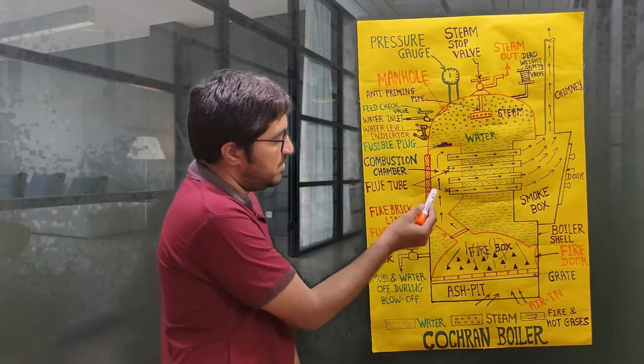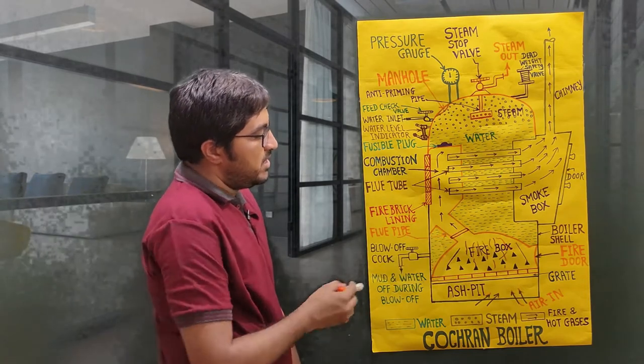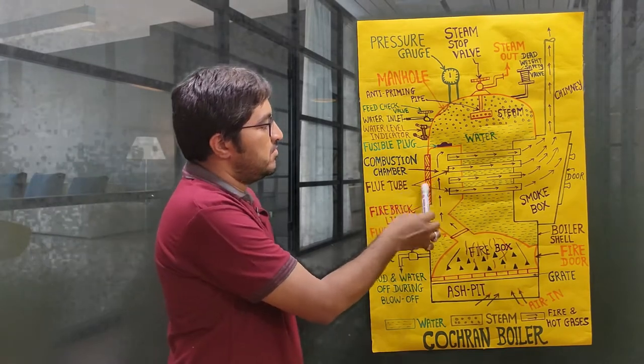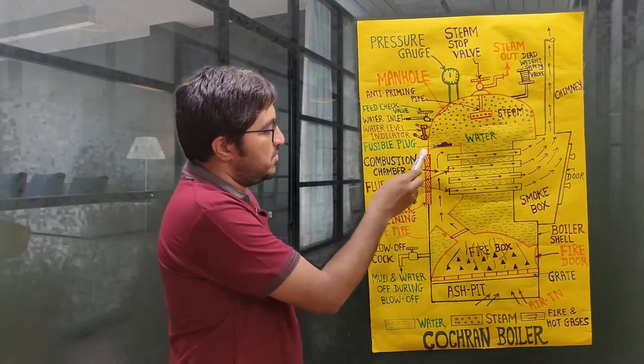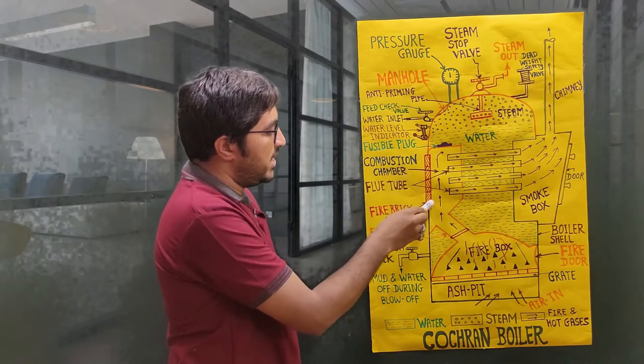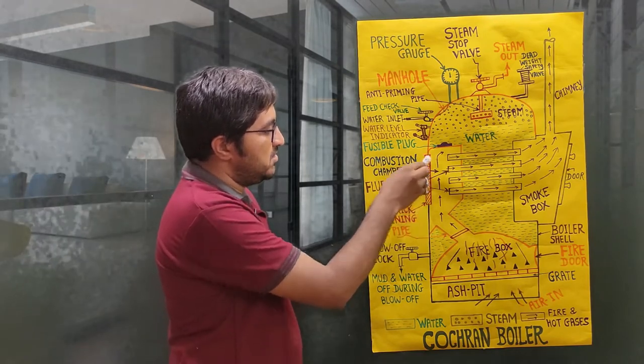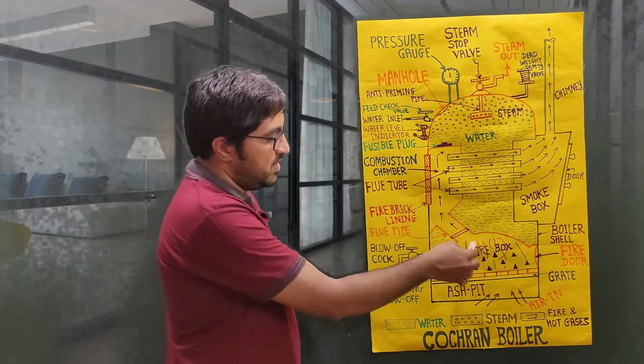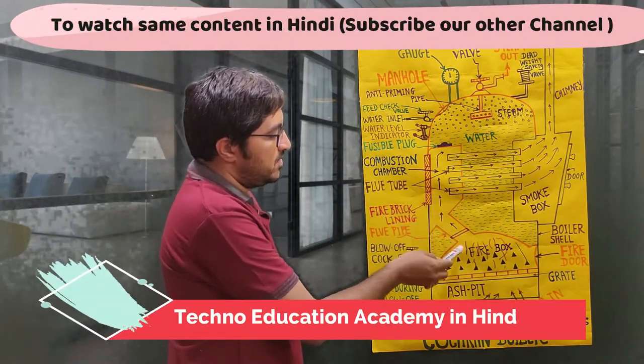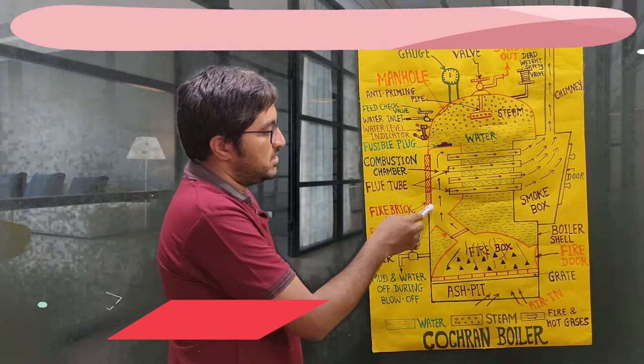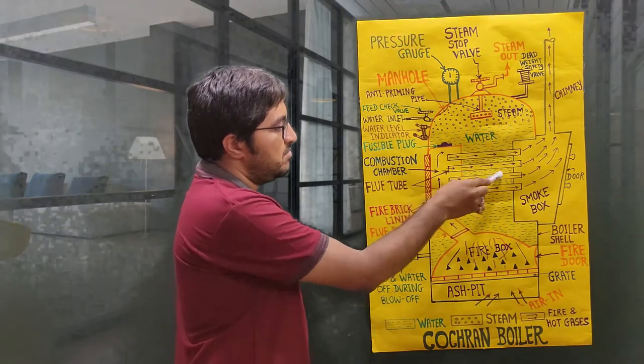The flue pipe connects the firebox with the combustion chamber. One side of the combustion chamber has a fire brick lining material. The function of these fire bricks is to deflect the flue gases coming from the firebox through the flue pipe. After deflection, the hot gases pass through the bundle of tubes.